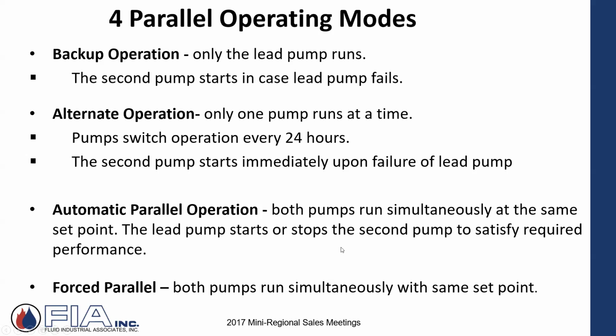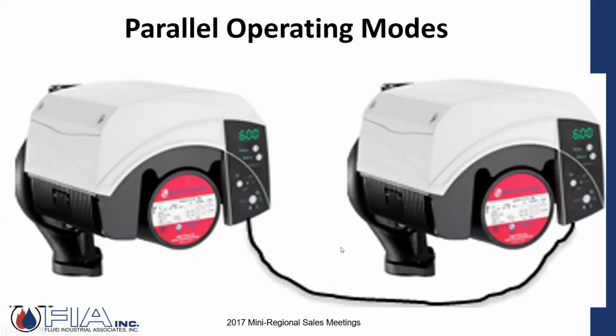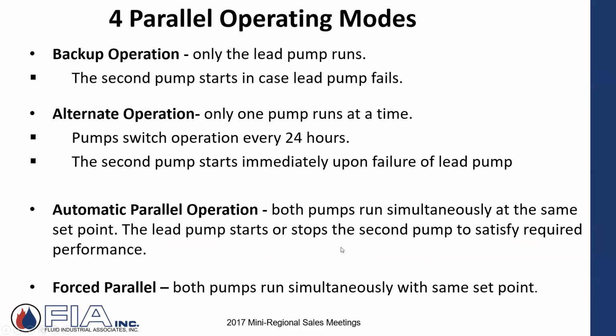The point with this technology and this smart is I have automatic parallel. I run them together, both pumps run simultaneously at the same set point. But as the load changes, conditions change, valves start to close, I don't need all of this. The lead pump starts and stops the second pump. So I can say, hey, we're running together at this set point, the conditions have got to the point where I'm pretty confident I can turn you off and I'll take care of the load. Now, as the load starts to come back online, more zones are calling. Okay, I'll bring it back on. We'll run in parallel. So there's a lot of intelligence with just these fairly simple 3 horse and under pumps.